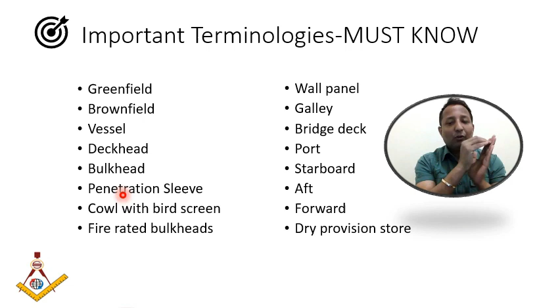What is cowl with a bird screen? It's provided where a penetration happens - you'll find a 45-degree cowl with a bird screen. The cowl ensures that if rain happens, water should not go inside the duct or opening, whether it's exhaust or fresh air ducting. The bird screen ensures birds don't enter and cause any accident. Cowls with bird screens are normally provided at the intake or exhaust of HVAC openings, for the air duct, or the fresh air intake or natural intake, whatever you call it.